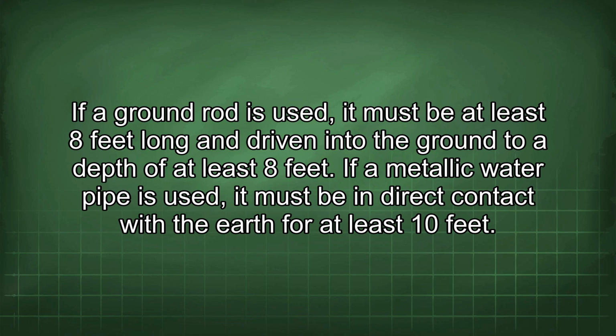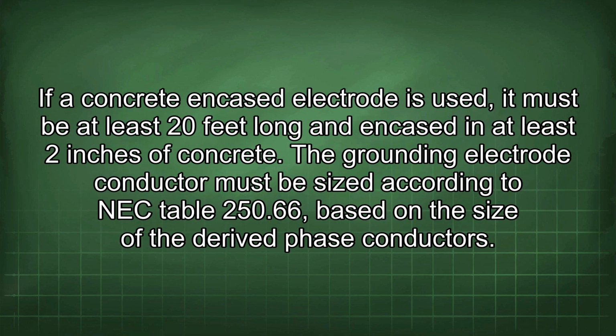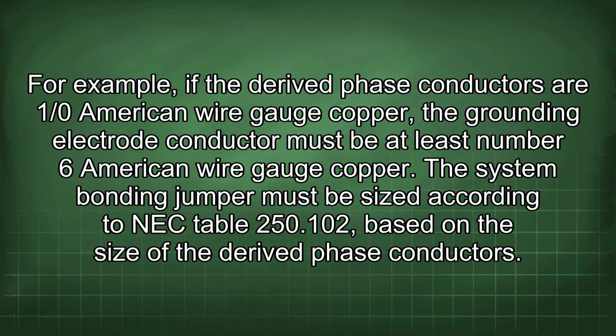If a metallic water pipe is used, it must be in direct contact with the earth for at least 10 feet. If a concrete encased electrode is used, it must be at least 20 feet long and encased in at least 2 inches of concrete. The grounding electrode conductor must be sized according to NEC Table 250.66, based on the size of the derived phase conductors. For example, if the derived phase conductors are 1/0 American wire gauge copper, the grounding electrode conductor must be at least number 6 American wire gauge copper.